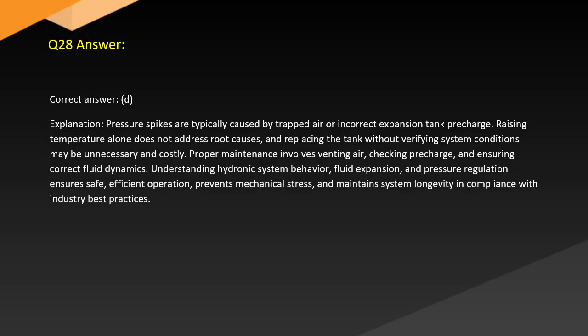Answer. Correct answer. D. Explanation. Pressure spikes are typically caused by trapped air or incorrect expansion tank precharge. Raising temperature alone does not address root causes, and replacing the tank without verifying system conditions may be unnecessary and costly. Proper maintenance involves venting air, checking precharge, and ensuring correct fluid dynamics. Understanding hydronic system behavior, fluid expansion, and pressure regulation ensures safe, efficient operation, prevents mechanical stress, and maintains system longevity in compliance with industry best practices.